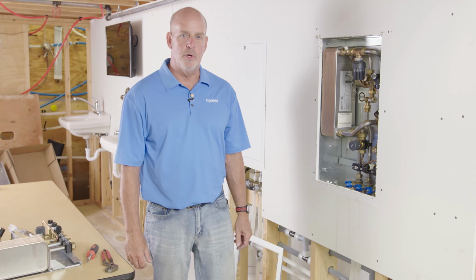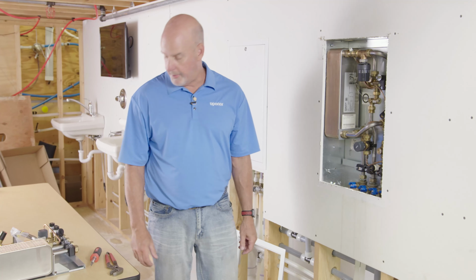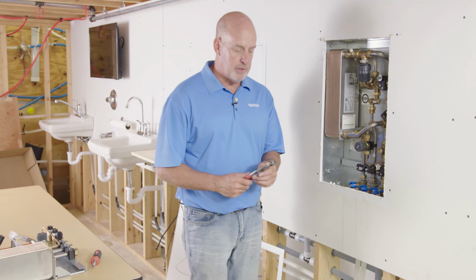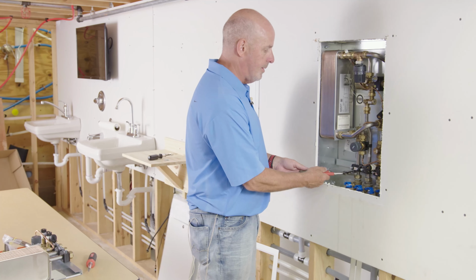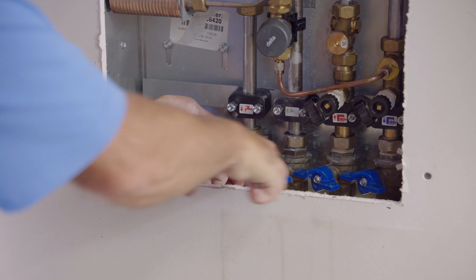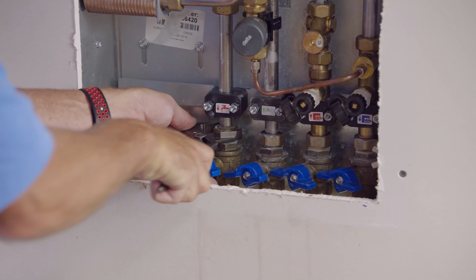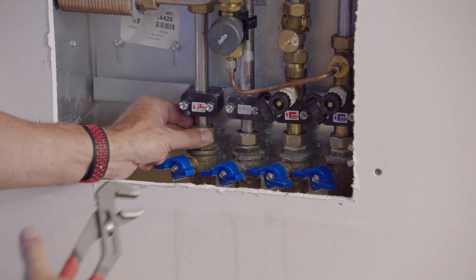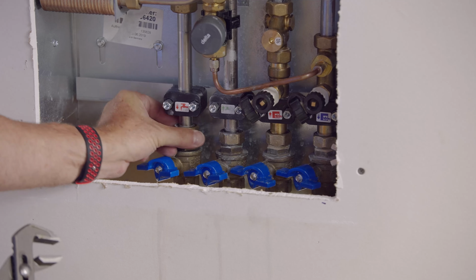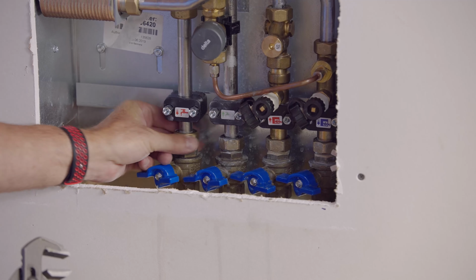Now that we've got the AquaPort unit drained, we're ready to disconnect it from the mechanical system. Recommend using a pair of pump pliers to loosen up the compression nuts. Be careful, there's going to be some water that's going to leak out of the system, so just be aware, have a bucket or some towels handy.